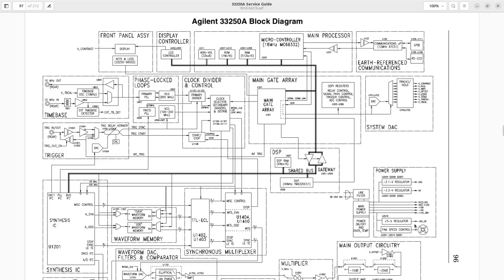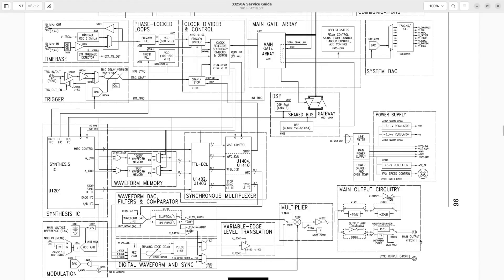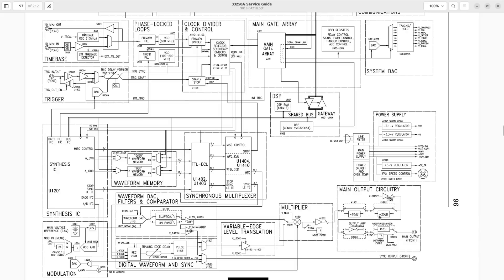Let's take a look at the block diagram. Here is the block diagram. And let's start from the output. Here is this main output connector. And here we have a protection, distortion filter, output amplifier, which can be bypassed. I believe it is only used in some ranges, when the output level is higher than a few volts peak to peak. And here we have a couple of attenuators, 10 dB and 20 dB. They also can be bypassed. And I think the error has to do with this relay around the 20 dB attenuator and this relay around the output amplifier.